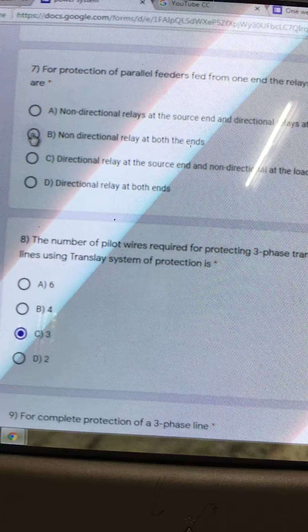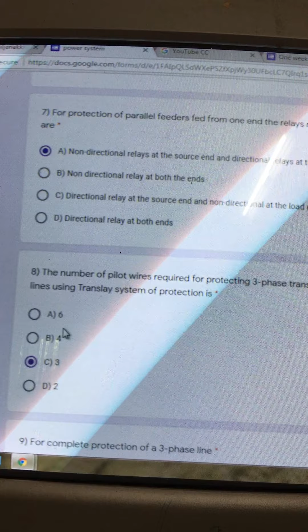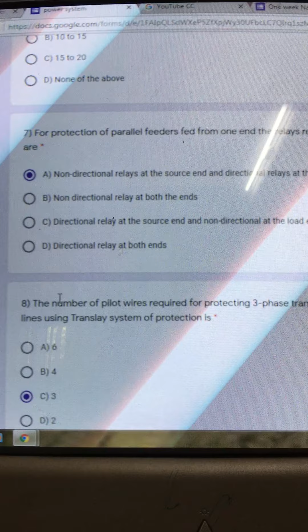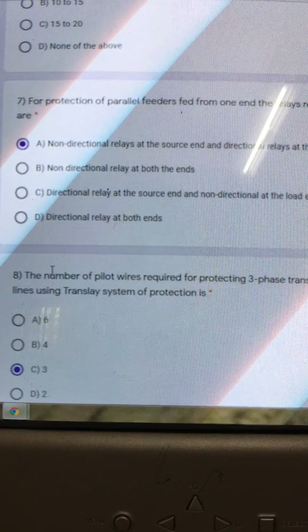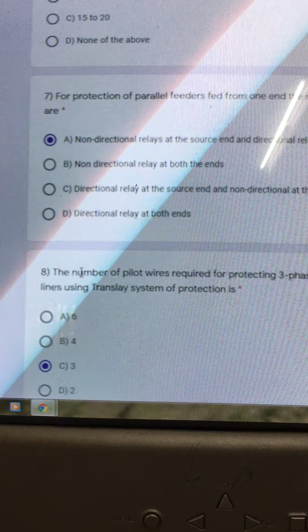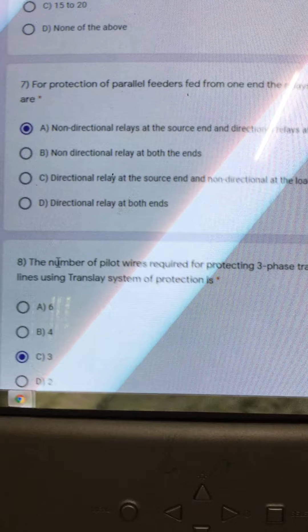Option A is correct. To repeat, for question number 7, for protection of parallel feeders fed from one end, the relays required are a non-directional relay at the source end and a directional relay at the load end. Non-directional relay operates irrespective of current flow, and directional relay prevents the flow of current back to the source.